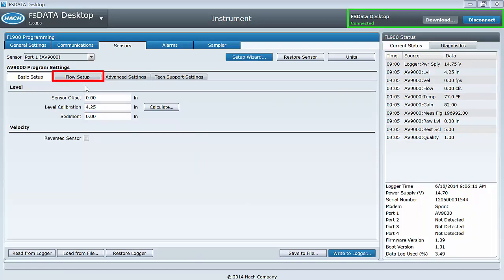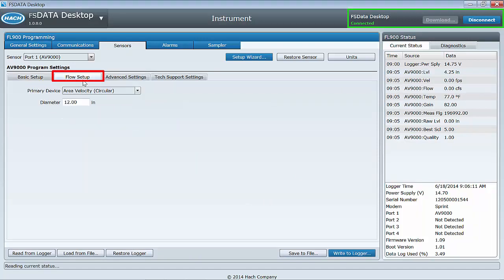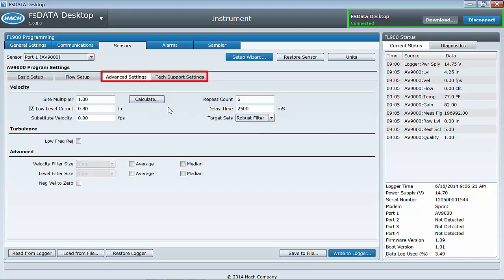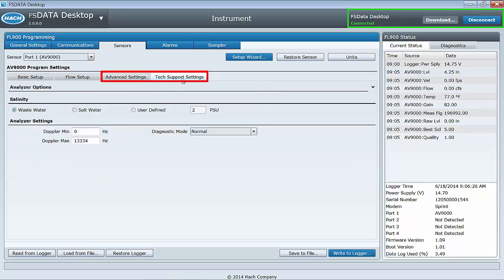The Flow Setup tab provides the input fields for the primary device, or more specifically, the channel geometry and flow calculation method. In greater than 90% of all installations, the Basic Setup and Flow Setup tabs are the only tabs that are needed. In sites with difficult hydraulics or less than ideal site conditions, it may be necessary to make adjustments to the Advanced and/or Tech Support Settings tabs.